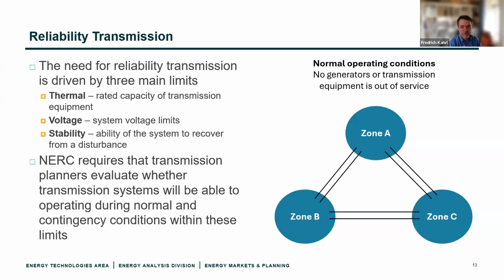Second is voltage - these are voltage limits set by a system operator, and we need to make sure the system is operated within these limits. Third is stability, which is the ability of the system to recover from a disturbance. So if we lose a generator or a transmission line, can the system recover to normal operations after an outage?